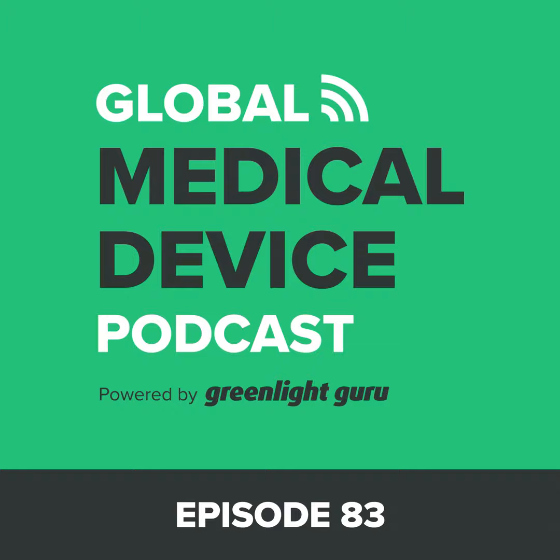All right. And so I think some key things for the listeners to take home on this is, if you think you're just focused on the U.S., that this doesn't matter, that's not true. It's still applicable to you. If you think that you're going to sell your products outside the U.S. and you're based in the U.S., you still need to meet that requirement. And if you're 13485:2016 certified or plan to become 13485 certified, but don't plan to sell into the EU, this topic is still a concern because there's that clause that you have to demonstrate that you're meeting the local regulatory requirements. There's very few words in the regulations or in the ISO requirements, it's not super expansive as far as this. There's just a few words, but those few words make a big difference. Yeah, they certainly do.